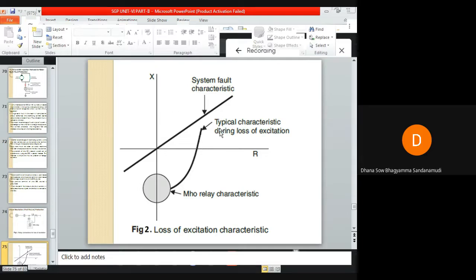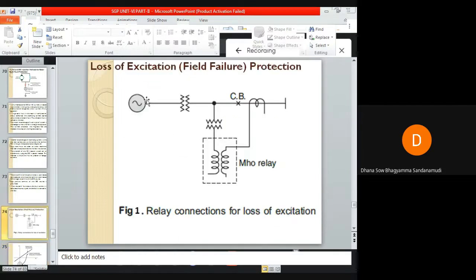During normal operating condition of the synchronous generator, the generator is supplying lagging reactive power and active power, and the power factor is lagging. Now if excitation failure occurs, then the synchronous alternator will start to work as an induction generator, and it will start drawing lagging reactive power from the grid. Instead of giving to the grid, it will take lagging reactive power from the grid. Of course, it will be supplying the active power to the grid. Hence it will operate at leading power factor. So when it is operating as an induction generator due to loss of excitation, it will operate at leading power factor.